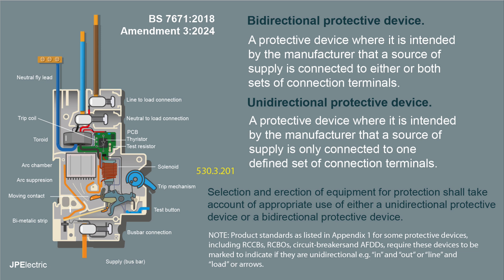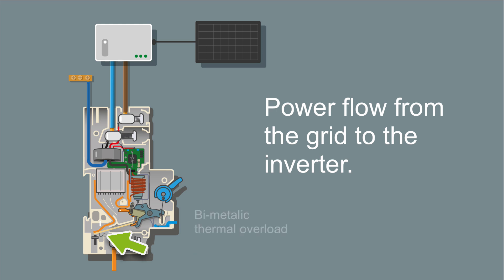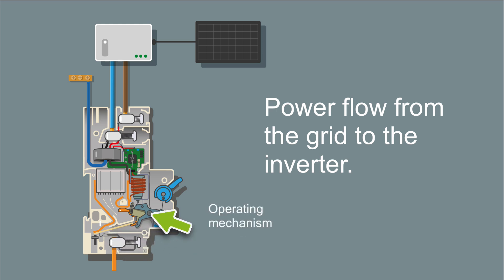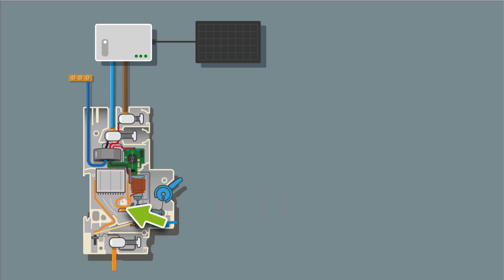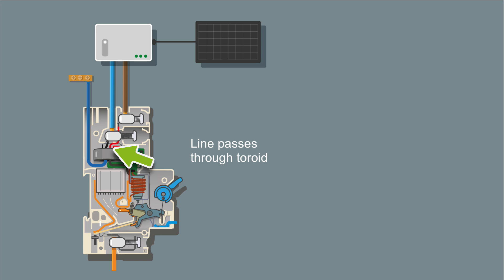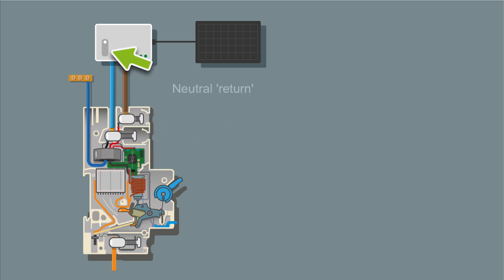Let's have a quick look at the flow of power through an RCBO. Power comes in on the bus bar, onto the bus bar terminal, goes onto the bi-metallic thermal overload, through the operating mechanism, there's the moving contact, goes through that, through the solenoid coil, then the live goes through the toroid, onto the line load terminal, and onto the load. It returns on the neutral back through the toroid.